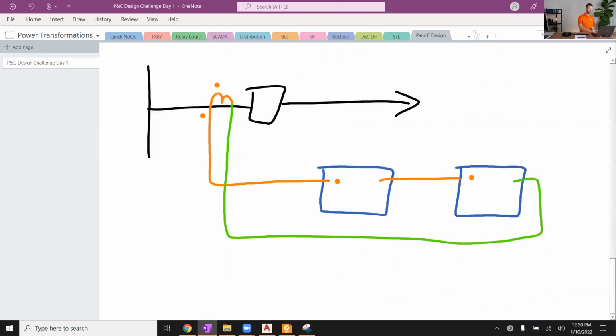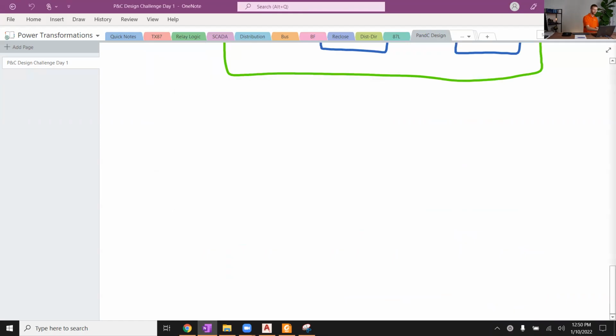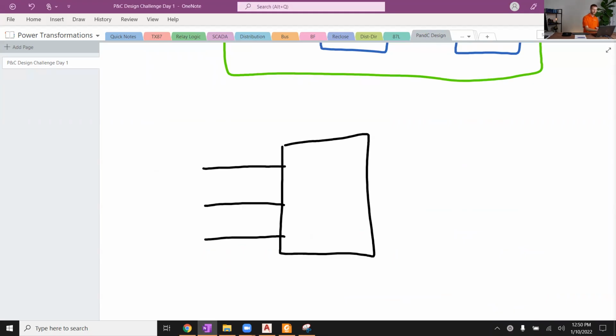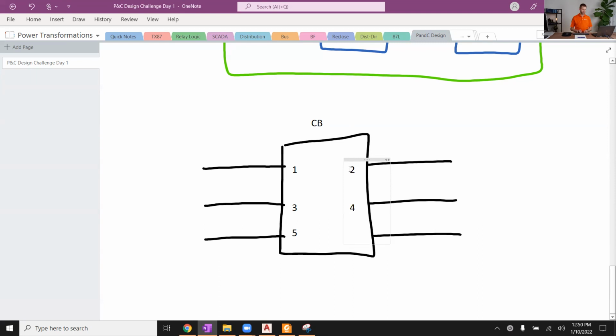I'm going to draw up a breaker for you. I told you I'd go a little further into the breaker bushings. Circuit breaker with phase A, B, C, in and out. So this is our circuit breaker. This is going to be bushing 1, 3, and 5 on the one side. And it's going to be 2, 4, and 6 on the other side. So 1, 3, and 5 would be coming in source side if that was the bus side, and then 2, 4, 6 would be going out load side, line side, if this was like a transmission circuit breaker.